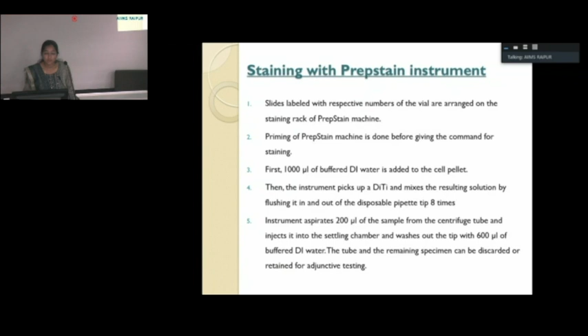Then the instrument aspirates 200 microliters of the sample from the centrifuge tube and injects it into the settling chamber, and washes out the tip with 600 microliters of buffer deionized water. The remaining specimen can be discarded or retained for adjunctive testing. The sample is allowed to settle onto the slide for a minimum of 10 minutes. During this time, the cells bond with the PrepStain slide coating and form a thin layer of cells. The instrument then adds 600 microliters of alcohol wash to the sample and evacuates all the remaining fluids. The sample is then allowed to dry for approximately 60 seconds.